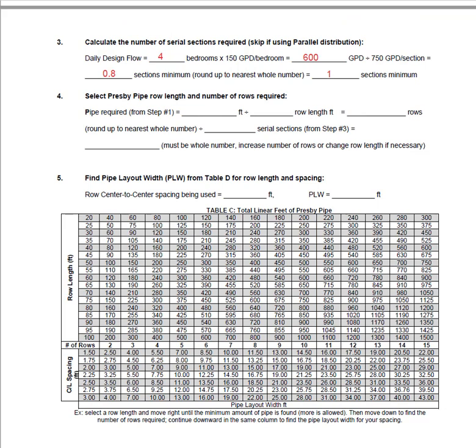In step number four we're going to determine our pipe row length and how many rows we will need. We're going to pull the value from step one — 280 feet of pipe — and divide by the row length we have selected. The rows should be as long as the site will accommodate, with a maximum row length of 100 feet. For this example we have selected a row length of 70 feet. Dividing our total required pipe by 70 feet, we find that we need four rows. We then divide this by the number of required serial sections from step three, which was one. We need one serial section of four 70-foot rows.